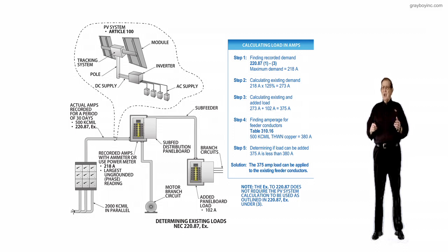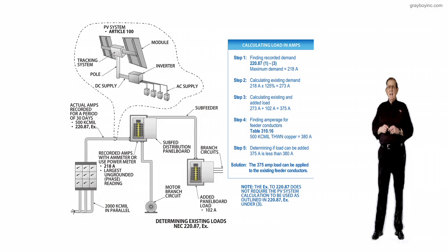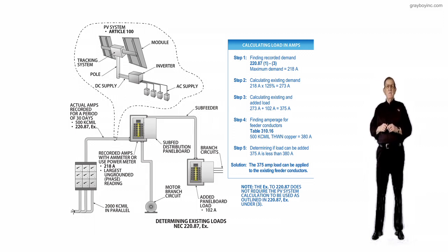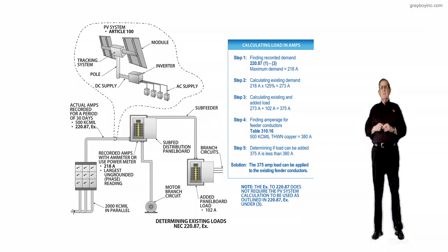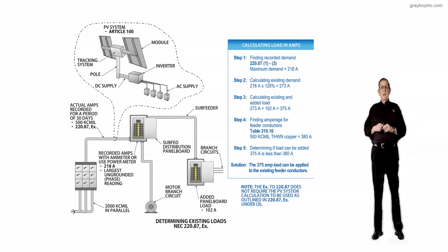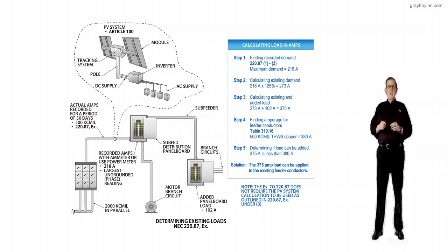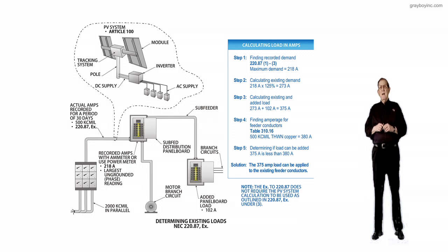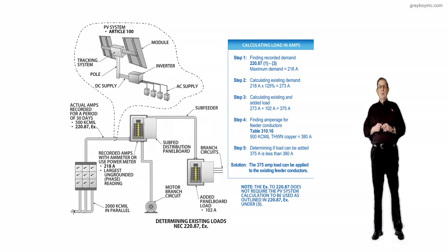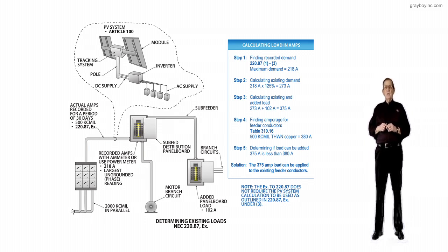The purpose of change is to provide a new exception which has been added to clarify that any feeder or service that includes any form of renewable energy systems or peak load shaving systems has effectively altered the actual peak load demand which is seen by a meter, such that the maximum demand data available does not reflect the actual peak demand for the feeder or service.